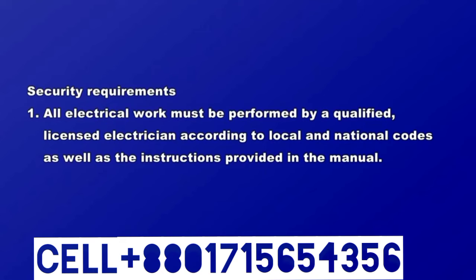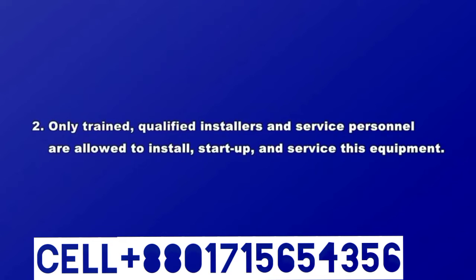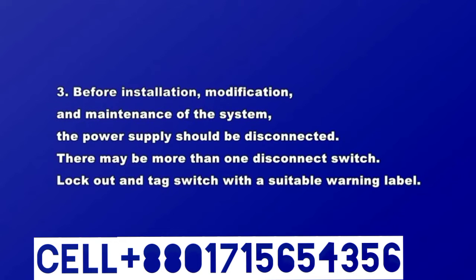Security requirements. First, all electrical work must be performed by a qualified, licensed electrician according to local and national codes, as well as the instructions provided in the manual. 2. Only trained, qualified installers and service personnel are allowed to install, start up, and service this equipment. 3. Before installation, modification, and maintenance of the system, the power supply should be disconnected. There may be more than one disconnect switch, lockout, and tag switch with a suitable warning label.